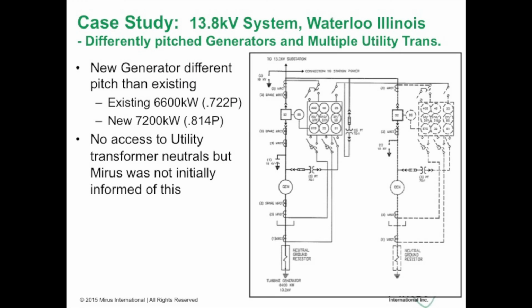And the final case study that I present is at a utility power station that was installing a new generator. They had an existing generator that was 0.722 pitch, and they were installing a new generator at 0.814 pitch. Quite large generators, on a 13.8 kV system.